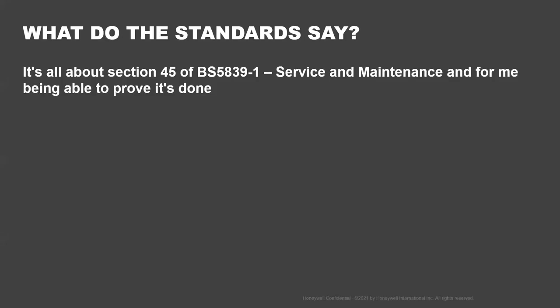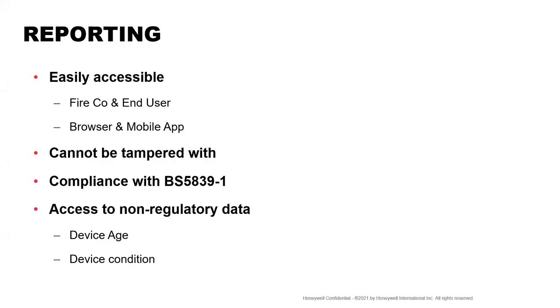So what do the standards say? Well, it's all about section 45 of BS 5839 part one, service and maintenance. And for me, it's being able to prove that it's done properly. So the reporting functionality of any online portal should be clear, concise, and easy to interpret. You've got to be able to understand what it's telling you quite easily. It needs to be readily accessible to those that need to get hold of it, with no difference in any way in the report available, both to the end user as well as the service and maintenance company.